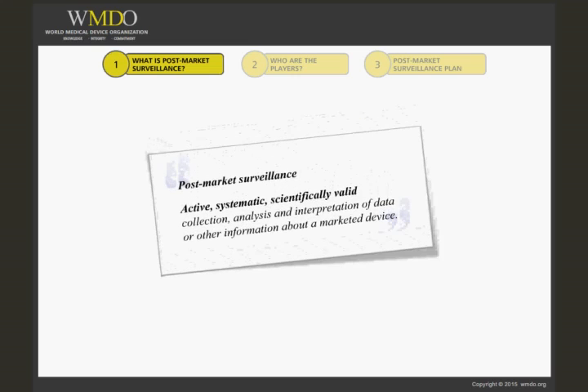Not many regulations have clearly defined post-market surveillance. The U.S. Code of Federal Regulations Part 822 lays out the rules for post-market surveillance for products that are put on the market in the USA, and provides the following definition: post-market surveillance is the active, systematic, scientifically valid collection, analysis, and interpretation of data or other information about a marketed device.